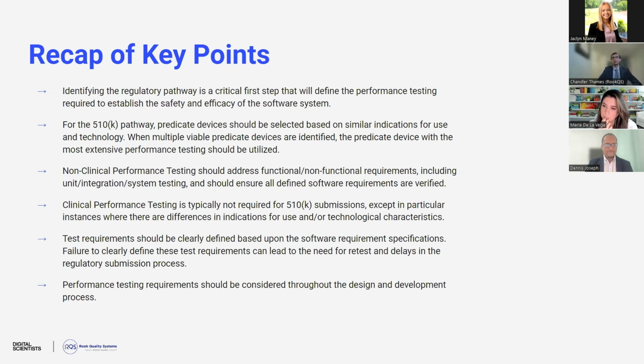In terms of test requirements for both non-clinical and clinical performance testing, definitely want to make sure that these are clearly defined based on the software requirement specifications. If you fail to clearly define these test requirements, it can lead to the need for retest, which will cause delays in your regulatory submission process. And performance testing requirements should definitely be considered throughout the design and development process to make sure you're not designing yourself into a hole where you can't provide performance testing to demonstrate the safety and efficacy of the system.